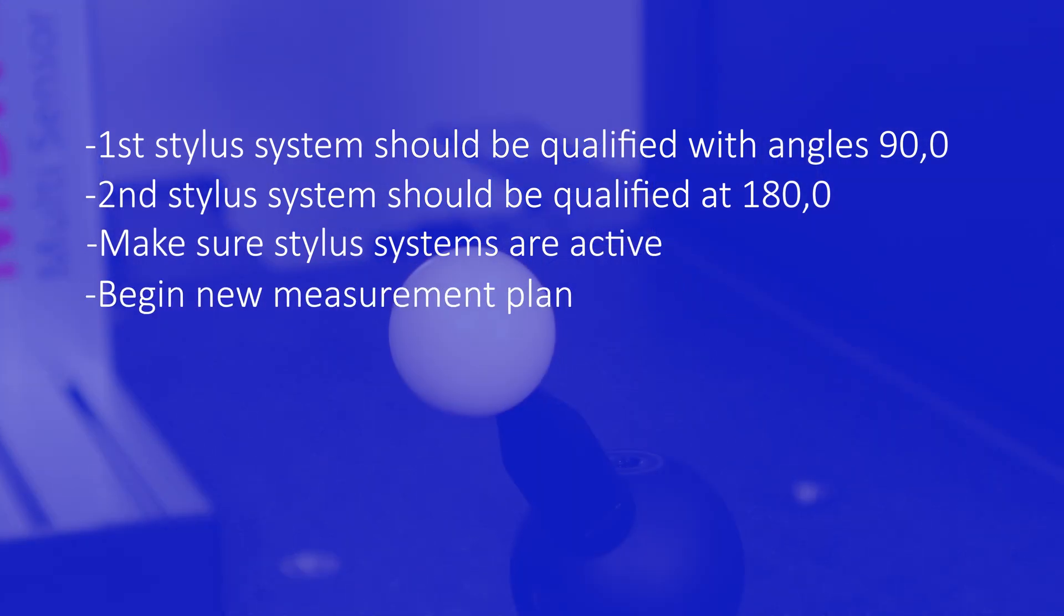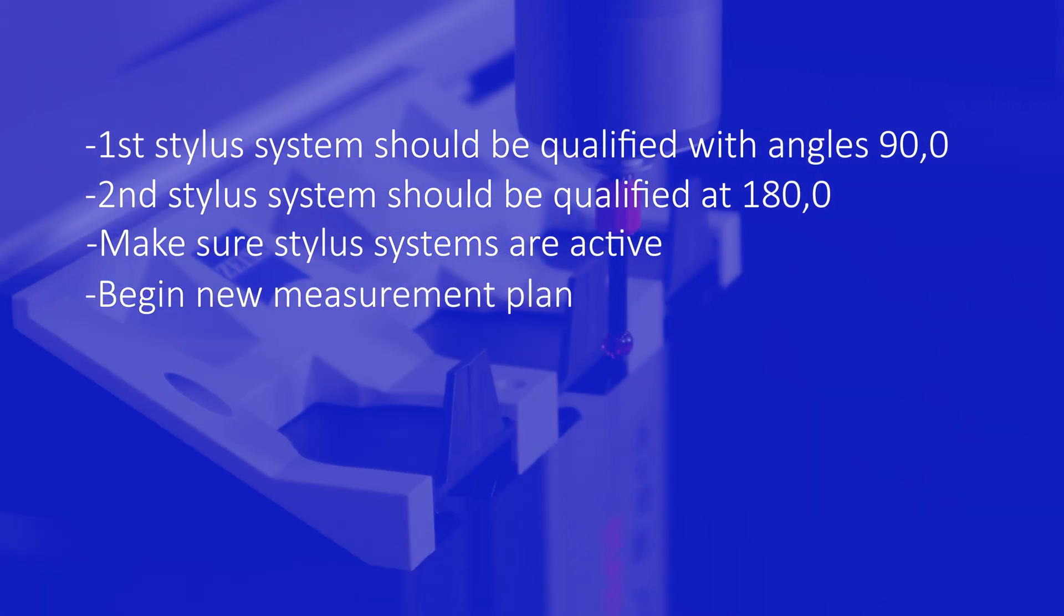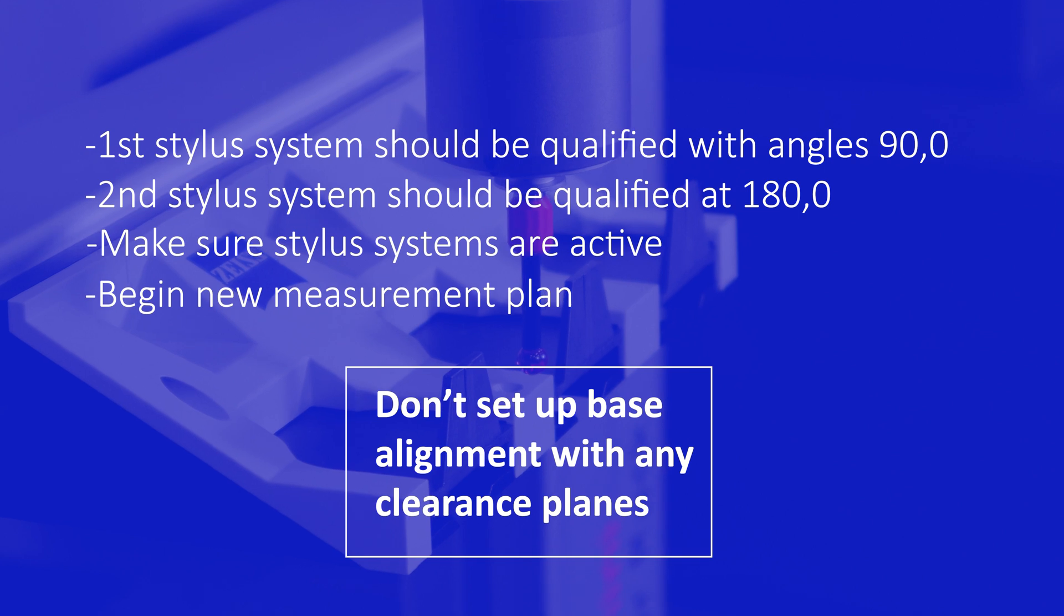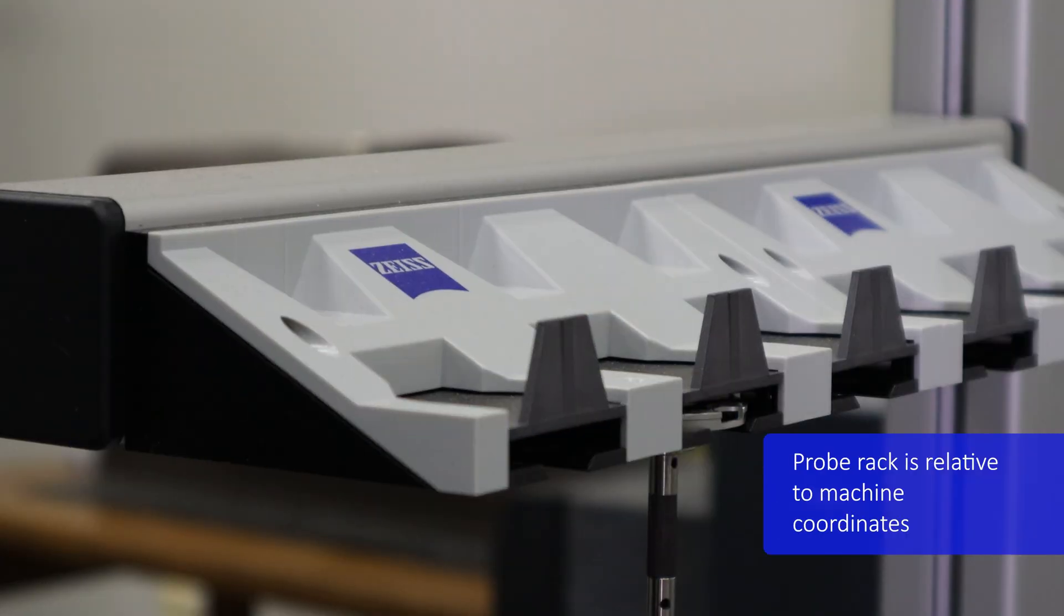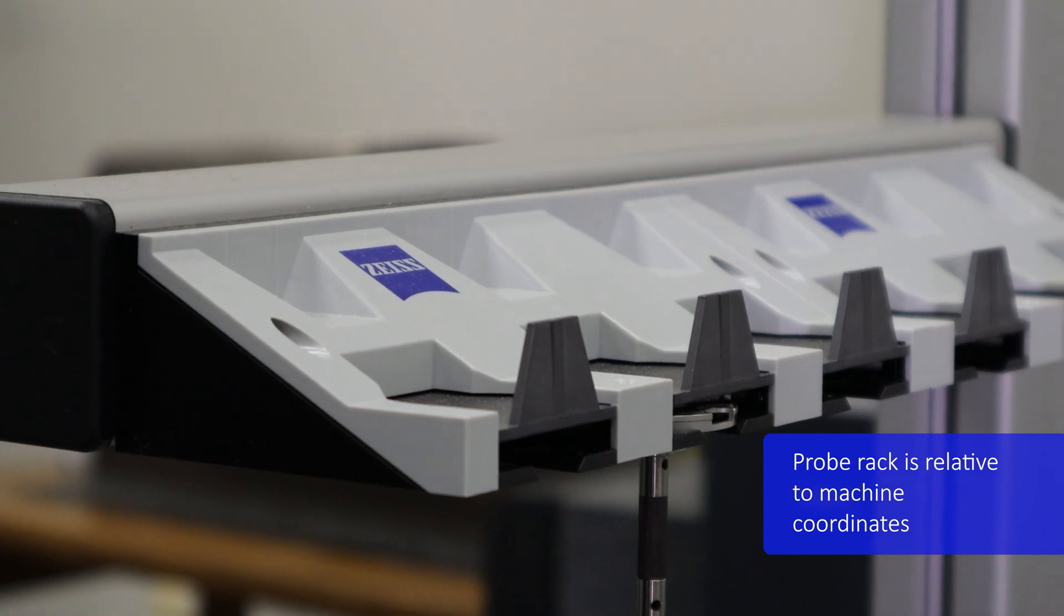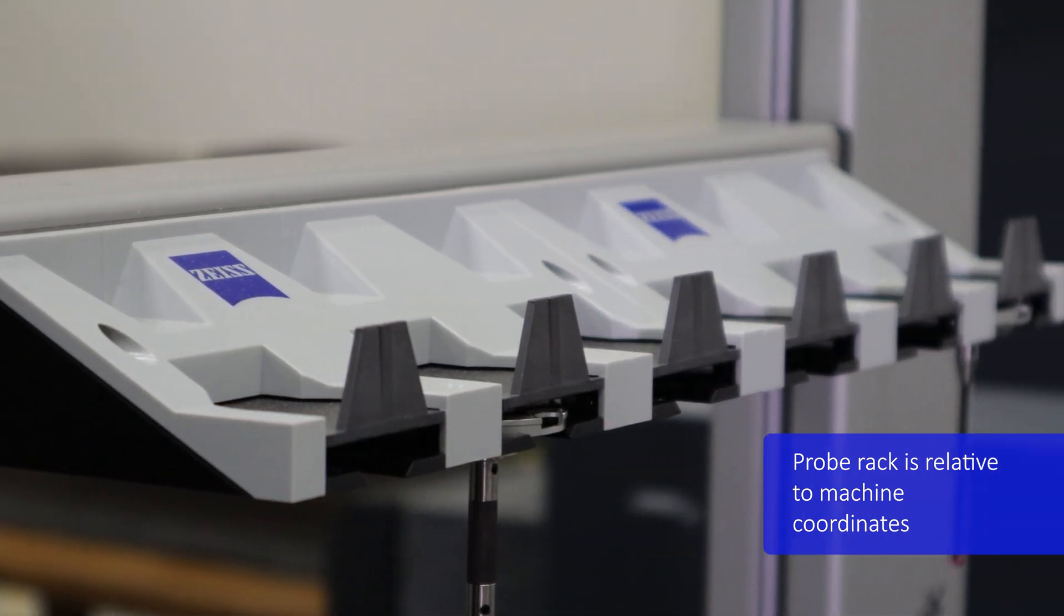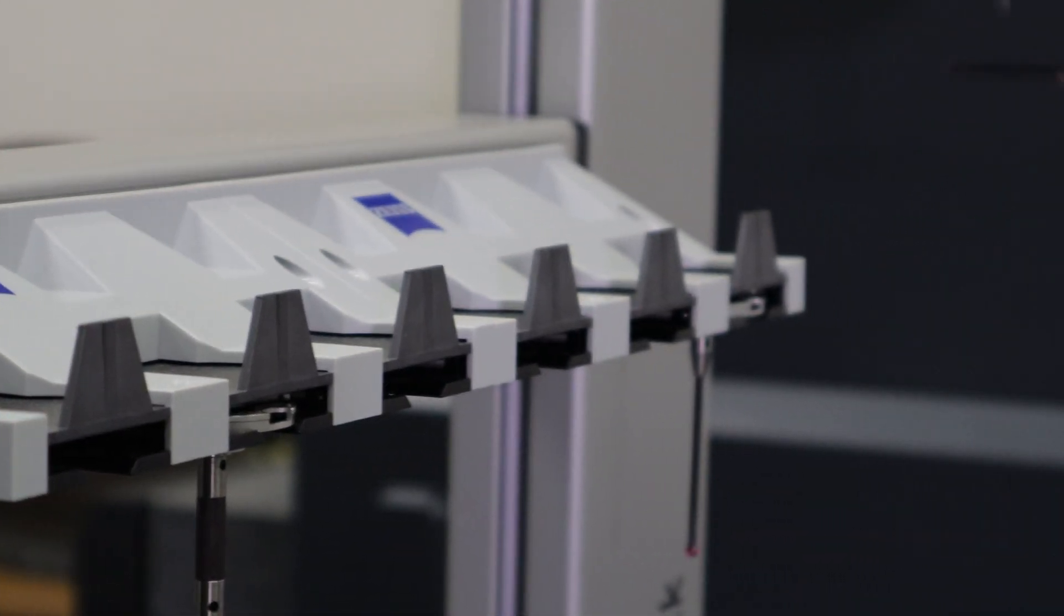Then begin a new measurement plan, sometimes called a program. Don't set up a base alignment or any clearance planes. The reason is your probe rack is going to be relative to machine coordinates, so you cannot set up a base alignment or clearance planes when you start your new measurement plan.